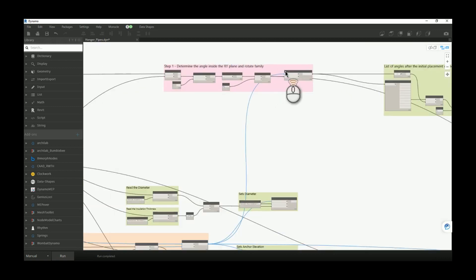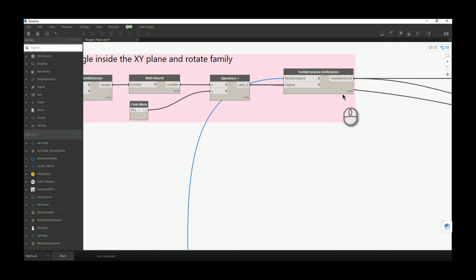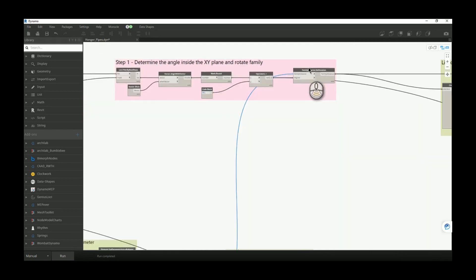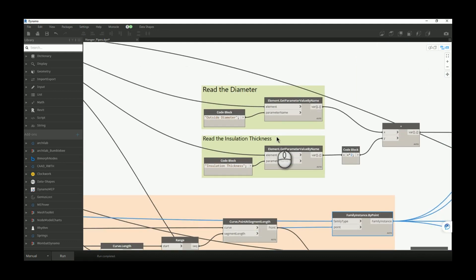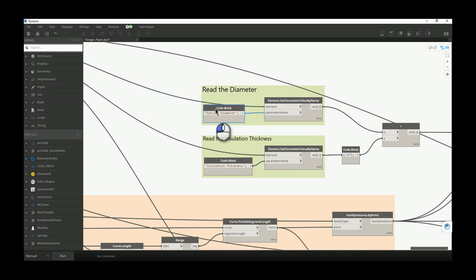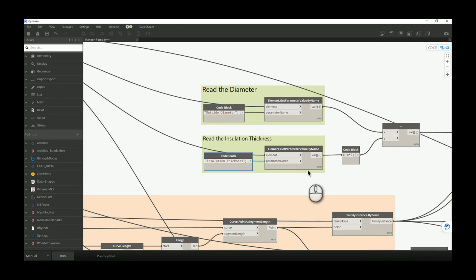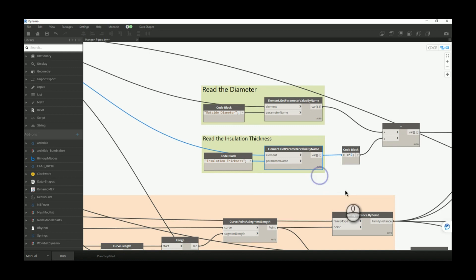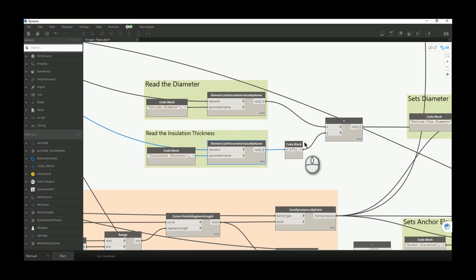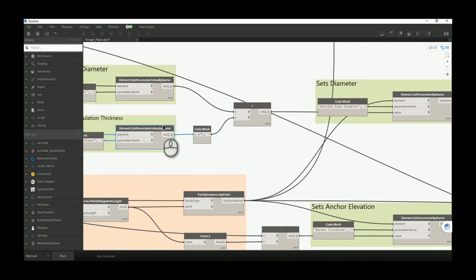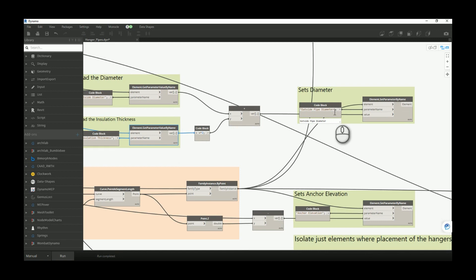We initially rotate all pipe hangers by 90 degrees with this value. Before we continue, let's see what we skipped. We did read the diameter of all pipes. We also read insulation thickness — there is only one pipe with insulation and the thickness is 25 millimeters. Because you have thickness on both sides, I multiply that by two. Now I know the outside diameter for my pipe hanger and I pass all those values to the pipe hanger family.